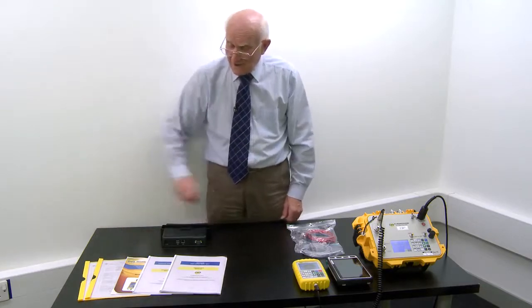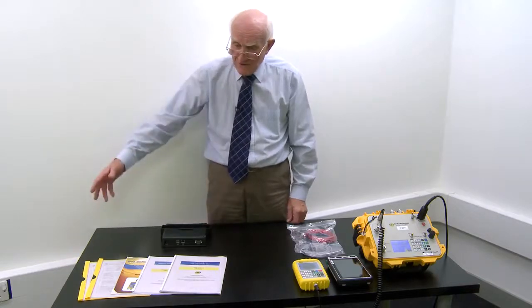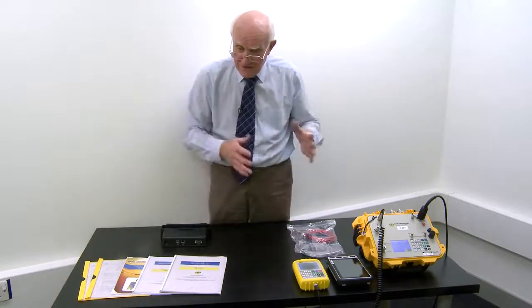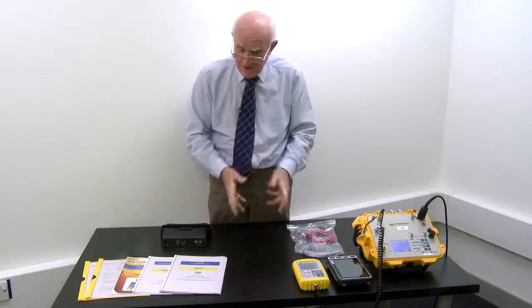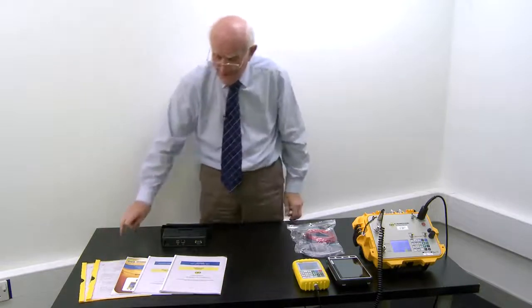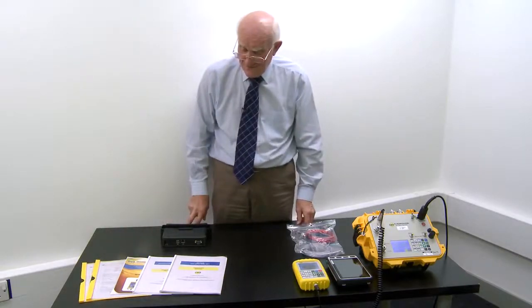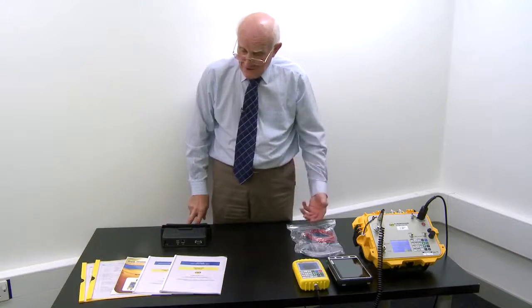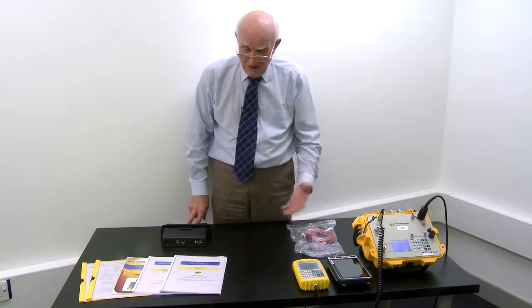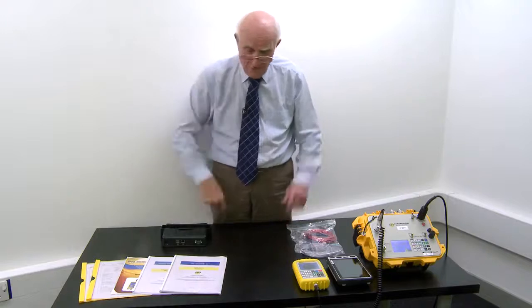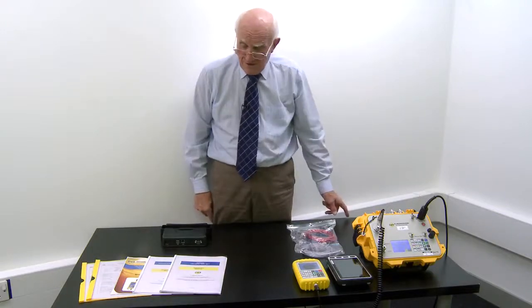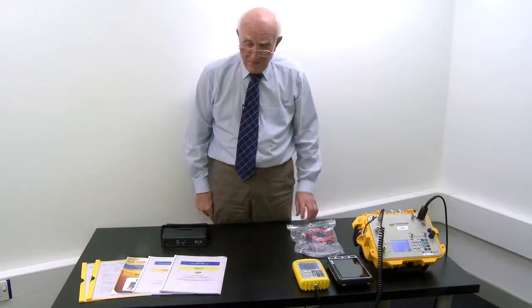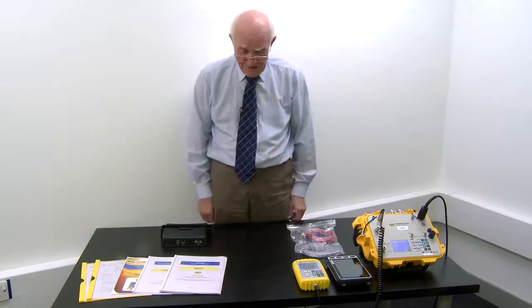We can supply, if you want it, the previous calibration for an instrument that's been in service. When it's brand new, of course, it would be just one calibration sheet. If it's an instrument that's come in for repair or maintenance, we can give you the previous calibration sheet and the present one so you can see any difference.